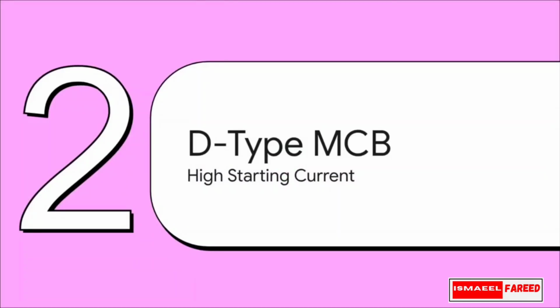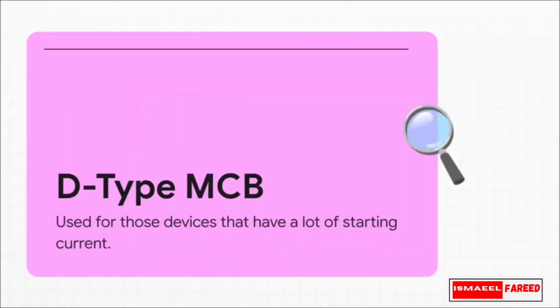Moving on to number 2, the D-type for high starting current. Now we're stepping up the power scale to the absolute heavy lifter. The D-type MCB is incredibly heavy-duty. It's used for devices that draw a massive amount of starting current. To put this into perspective, if you tried to plug a D-type appliance into the C-type residential breaker we just talked about, that huge initial power surge would instantly trip the breaker and shut your whole house down. The D-type is engineered specifically to absorb that huge initial jolt, making it absolutely essential for industrial applications.